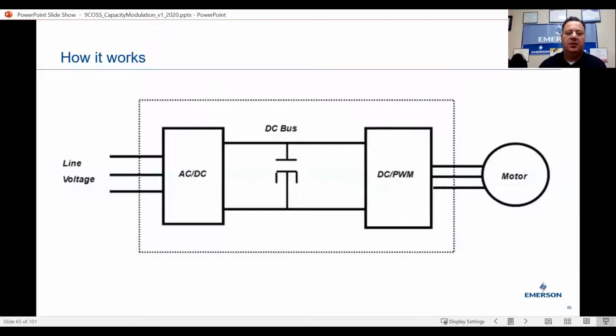All right, how does it work? Again, we can either have three-phase or single-phase coming in on the line. But at the end of the day, at least with our drives and our variable speeds, we're going to be throwing three-phase out at the end. So we're going to convert it from AC to DC, and then we're going to invert it back to the motor as three-phase. So whether it's single-phase or three-phase coming in, the motor will see three-phase on our compressors, all right? That's how it works.